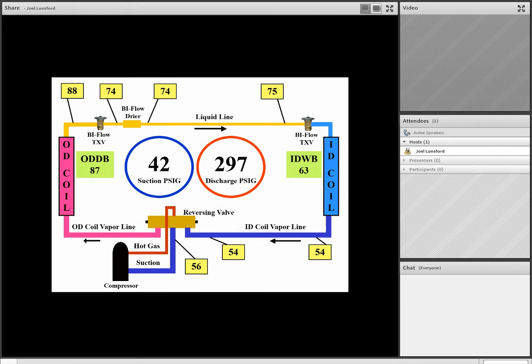We have high superheat. We also have low suction pressure. We also have high discharge pressure and elevated subcooling levels. So as we take a look at our diagnosing system problems, you see that you have low suction, high discharge or liquid line pressure, superheat is high, and we have an elevated or high subcooling. And so if we look at that closely, we know we have a liquid circuit restriction of some kind. So we can narrow our focus down now to the liquid side of the system.